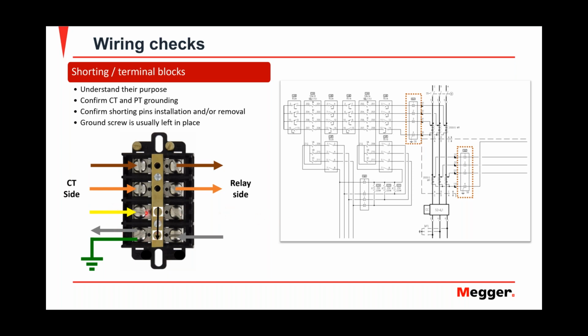So now your relay doesn't see C-phase. Your current is physically being shorted via this bar. Then you go in and you do your B phase, you put the screw in, and now you're shorting B and C phase. And then you do your A phase, and now your relay is completely isolated. And then you could come over here if you want, and you could inject from your relay test set currents into your relay. Now you have to take it apart.